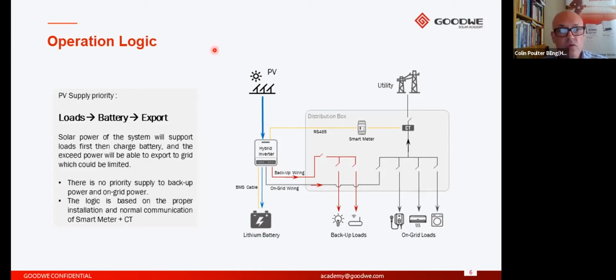So the way this works: let's consider we have some loads running, and the amount of power being generated by the inverter from the solar panels is actually greater than what's needed by the loads of the building. I should also mention there's no priority between the backup loads and the on-grid loads, so power supplies equally to either side. So we've got this excess power.